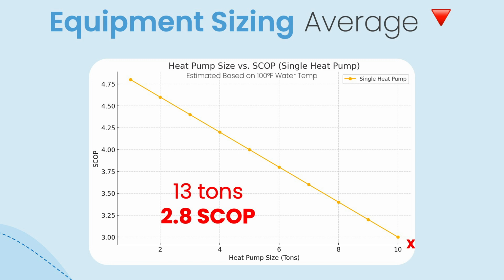It's kind of hard to fit it on this, but the SCOP is really low there, and you might think it's still turning 1 kilowatt into 2.8 of heat output, but electricity is more expensive than gas, and they're investing quite a lot in this system, so they're going to be very unhappy if they get that installed. And there's more to come yet to show it probably wouldn't even operate at that. Comparatively though, first of all, just on the face of it, the award-winning heat pump designer, if we plot 4.5 tons there, they're getting 4.1 SCOP. So again, it's good. Anything above 4 I think is good, what people aim for. So every kilowatt that goes into it, you're getting 4.1 out of it in terms of heat output.